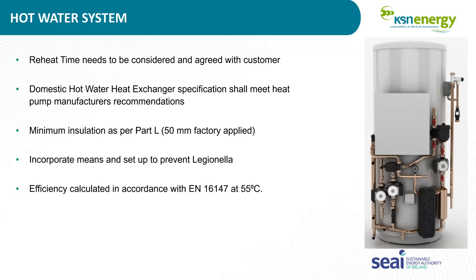There has to be a means of Legionella prevention. Again, I think it's about 55 degrees. Water stored below 55 degrees has a risk of Legionella. The heat pump is probably heating the hot water to about 45 degrees, so there needs to be some means that at least once every 2 weeks the water gets heated to 60 degrees or higher. The manufacturers' controls generally control that. But sometimes there might be an existing cylinder there where the heat exchanger is adequately sized. And what an inspector will look for in that case is some sort of time control, possibly for an immersion to raise the temperature.